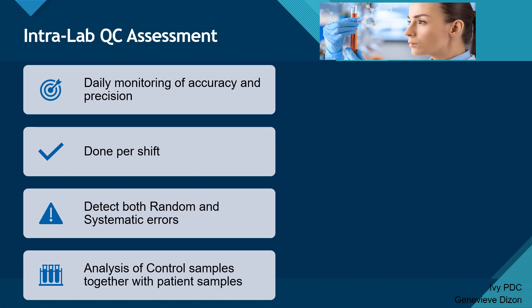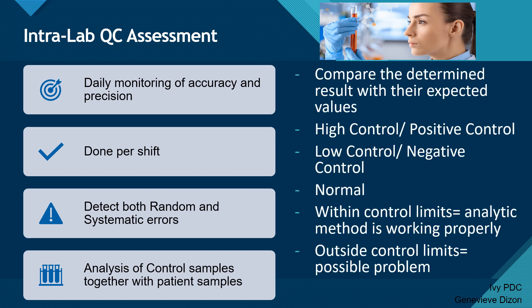Intra-lab can detect both random and systematic errors, as you will see later when we perform the charts. It also involves the analysis of control samples together with the patient samples. We compare the results and determine if they fit the expected value. Usually we have three different types of control materials: the high control or positive control, the low control or negative control, and the normal. These are all tested on all the analytes and all the machines, and then we determine if they are within or outside control limits.